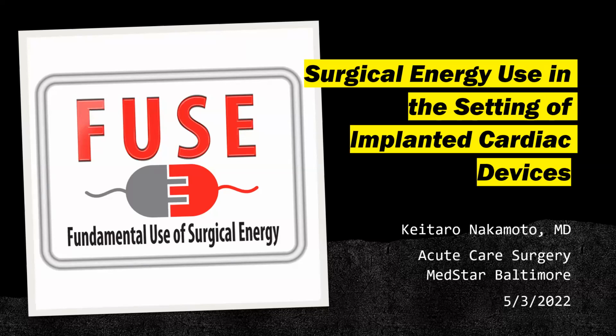The fuse exam will ask you many times: when you change between settings, typically 3 and 5 are the two settings on the ultrasonic device. You're not changing the frequency of vibration, it's always 55,500 times a second. There used to be a device at half that frequency, but they took it off the market.